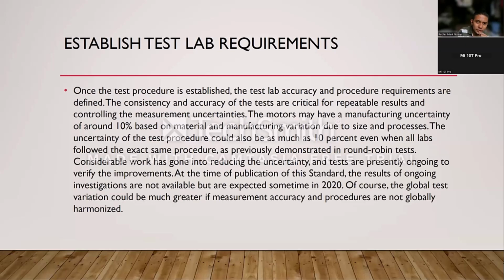Establish test lab requirements. Once the test procedure is established, so pag natapos na yung test procedure na yan, nagawa na the test lab accuracy, the procedure requirements are defined. The consistency and accuracy of the test are critical for repeatable results and controlling the measurement uncertainties. The motors may have a manufacturing uncertainty of around 10% based on material. Procedure could also be as much as 10%.